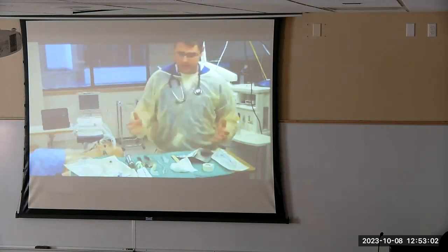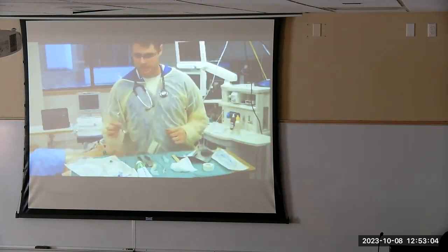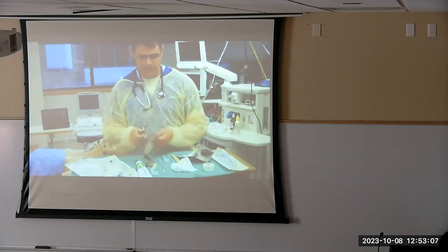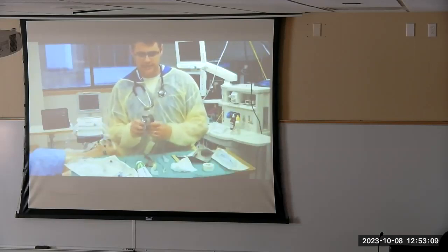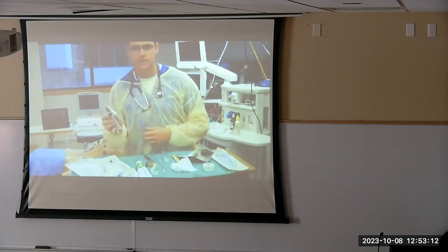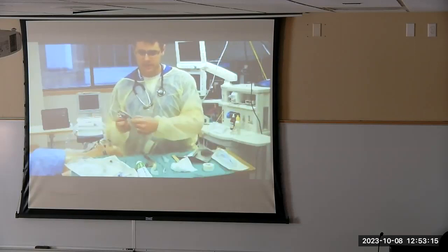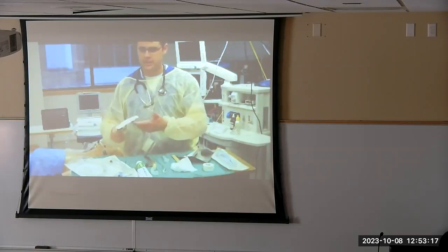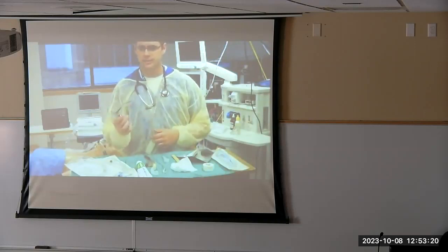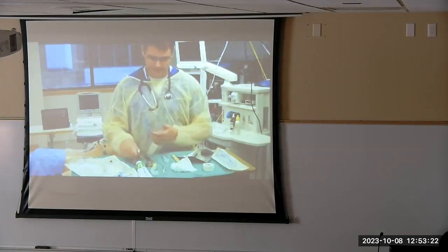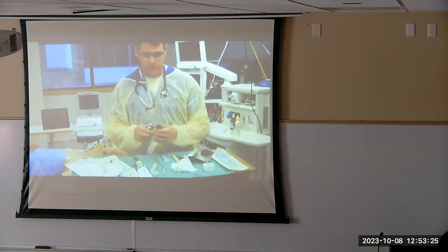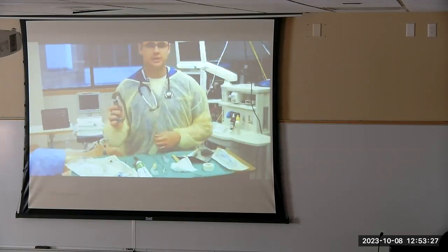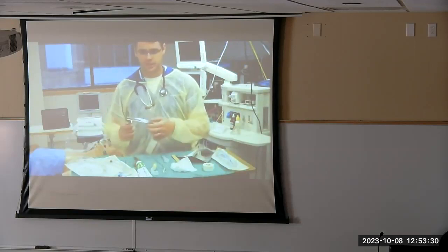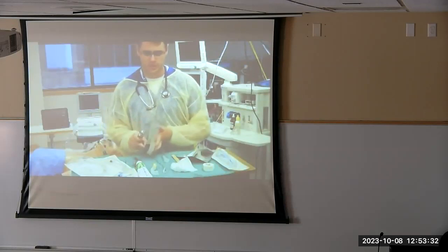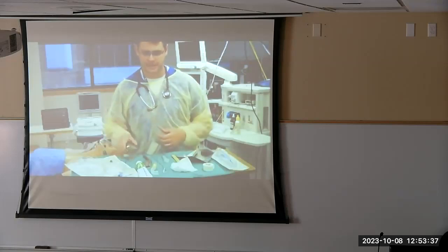Next thing I'm going to do is look at my actual instrumentation for laryngoscopy. You're going to need a handle with operating batteries and a blade that fits the handle. I'm using a standard handle and standard blade here. This is a Mac 3. I'm going to make sure the bulb is nice and tight on the distal tip. Flip it on and check that the light is working and that it's bright to your satisfaction. I have a number 4 blade in case I was unsure of the insertion depth, so I can also check that. Look at the bulb, tighten it, and make sure it's working appropriately. I'm going to leave the number 3 blade on because that's the most common one. I'm going to leave it in the disengaged position.